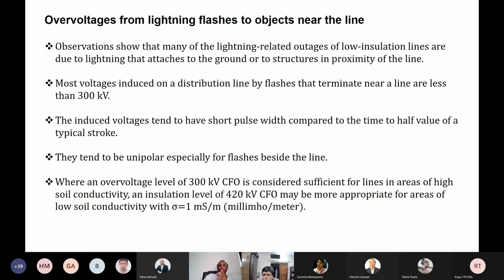Don't forget that this is the transient peak value, okay? The induced voltages tend to have short pulse width compared to the time to half value of a typical stroke. So don't forget that when you're calculating the induced voltage due to a certain lightning current, the induced voltage is proportional to the current derivative, so the induced voltage must have a duration quite less than that of the current waveform. Usually it can be like 1/4 of the duration of the current. They tend to be unipolar, especially for flashes beside the line.